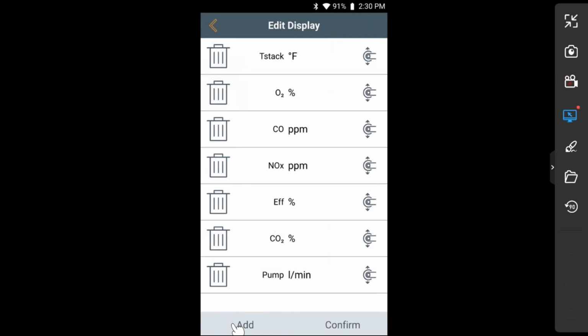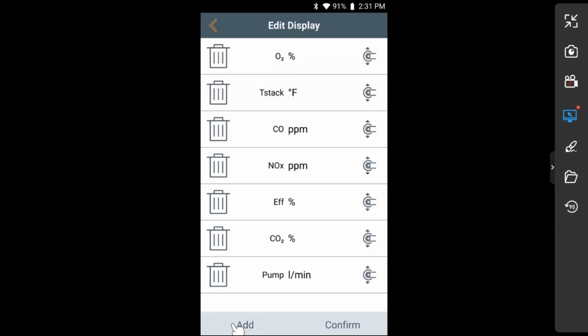Here is the display that I'm looking at. If I wanted to see oxygen as number one, I could press on oxygen and move it up, above stack temperature. What I do when I'm taking a test is look at 1, 2, 3, 4 as my major measurements or calculations. In this case, I have oxygen, stack temperature, CO, NOx, and then I look at combustion efficiency.